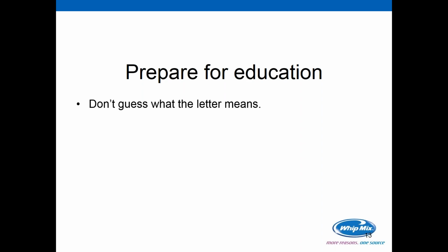As I pointed out at the very beginning, when we were looking up 21 CFR 820.30, if that were in your warning letter, you would need to look into this regulation and see what that regulation means. Some of the regulations are, I won't say vague, but to a person that is not immersed in the regulations every day, it could be confusing. It could be unclear what the agency is asking for. But again, don't guess what the letter means.